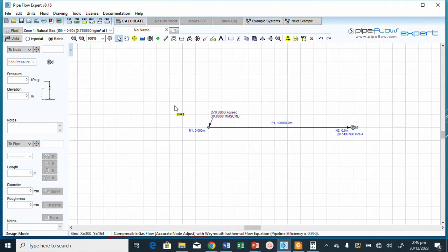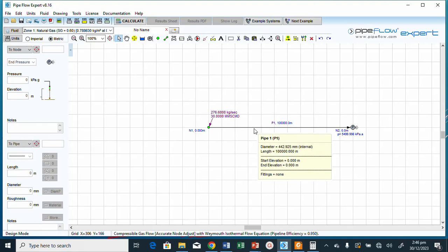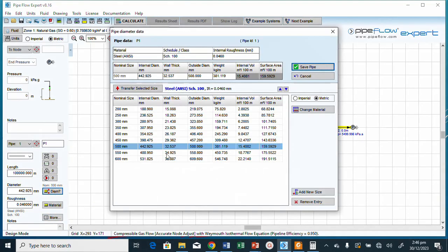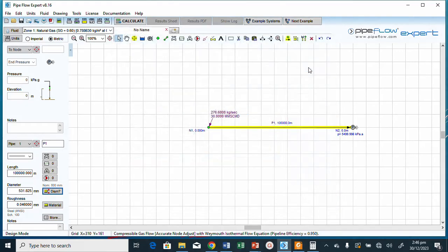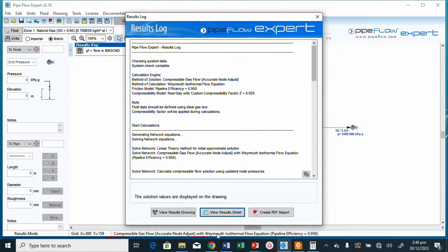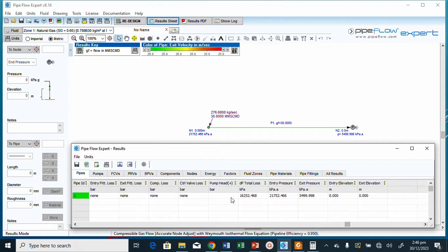Let's increase the pipe size further to 600 mm. Select, transfer selected sizing, click Save, then Calculate. The pressure drop is now about 16,000 kPa and the entry pressure is around 21,500 kPa — still higher than the 8500 kPa maximum operating pressure.